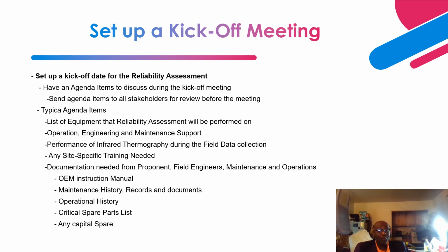I've run into hotspots whilst performing reliability assessment, and this is something that you wouldn't even know. You'd be waiting for the next calendar year or 6 months or 1 year to perform the infrared thermography on that equipment. And you'll be surprised that it was while we were performing the reliability assessment that we identified those hotspots on those equipment.